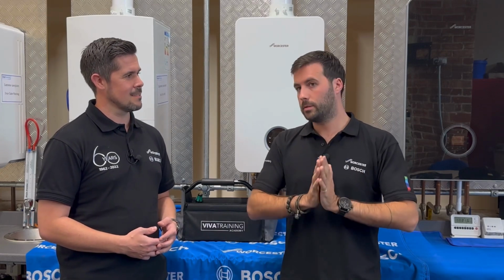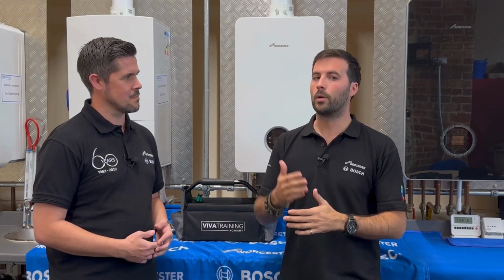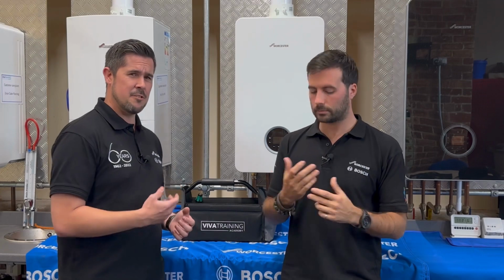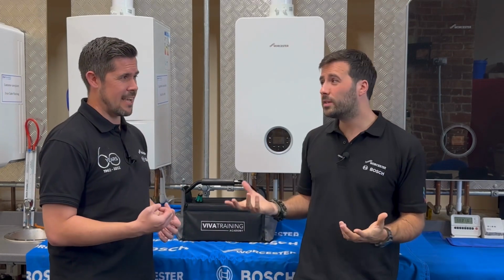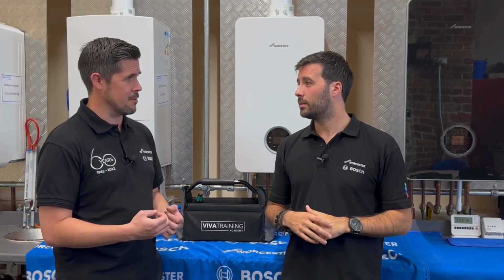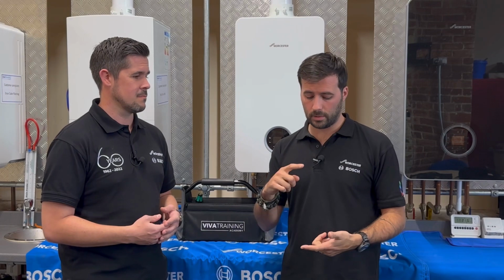EA faults can be a broad range of things, but only look at what would prevent a boiler from lighting. These are usually quite easy checks, very basic things we'd be doing at that stage - nice and easy for an engineer to do. In order to get a flame, you need fuel, you need air, and you need ignition. Start there - easy, perfect.